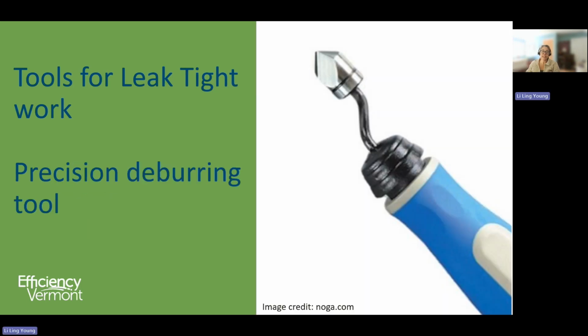I very rarely see any attention paid to deburring tools. Actually, sometimes I see them referred to as reamers, which sounds rough, like a rough process on the pipe. But the flare is a critical piece of the leak-tight system. Making a perfect flare starts with a perfect tube, perfectly round, perfect length, perfect angle, perfect thickness. Scratching up the inside of the tube end damages the material that makes your flare.